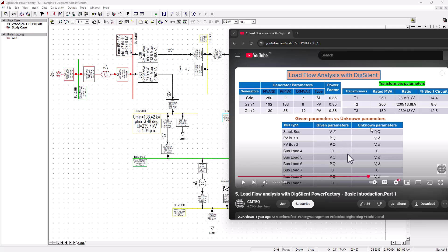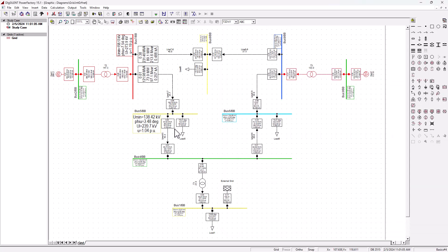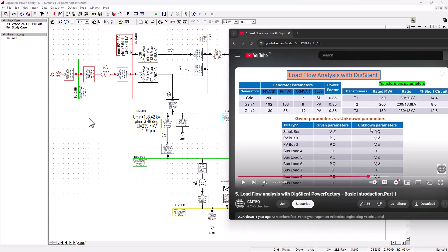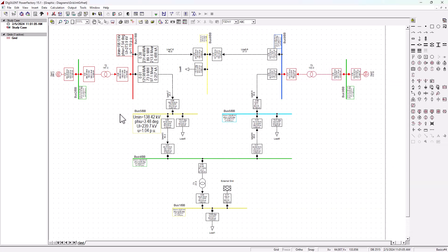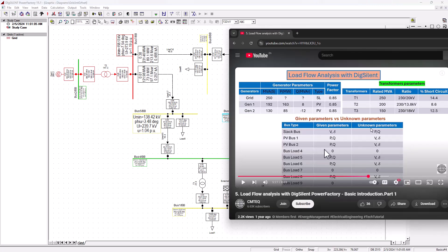However, I realized this could be misleading, and I appreciate the feedback from the community pointing this out. To clarify, in real-world scenarios or detailed analysis, Q for the PV bus is an unknown parameter. The generator's reactive power output is determined by the system load flow analysis based on the loading conditions and the generator's reactive power limits. Let's demonstrate by running this load flow analysis to show why Q is supposed to be an unknown parameter, not a given parameter.